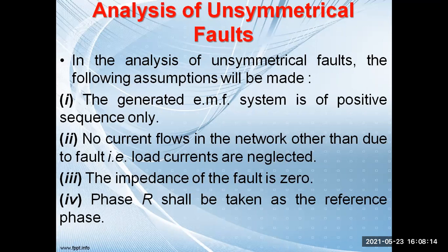Second, no current flows in the network other than due to the fault, and load currents are neglected. So we are assuming there is no load because the unsymmetrical fault has occurred. Third, the impedance of the fault is 0, and phase R shall be taken as the reference phase.